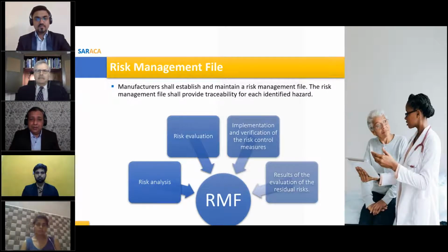I think if you have PMS data from the market which tells you that you better look at your DFMEA, PFMEA, and perhaps you might have to increase or reduce the risk associated with some of the harms and causes, right? In that case, you will have to update your RMF. So this is a very important file. I would recommend all of our viewers to please maintain a file. List all the documents which come under it, and make a periodic evaluation of the RMF. Your life will be a lot easier when you face an audit from a notified body or regulator.